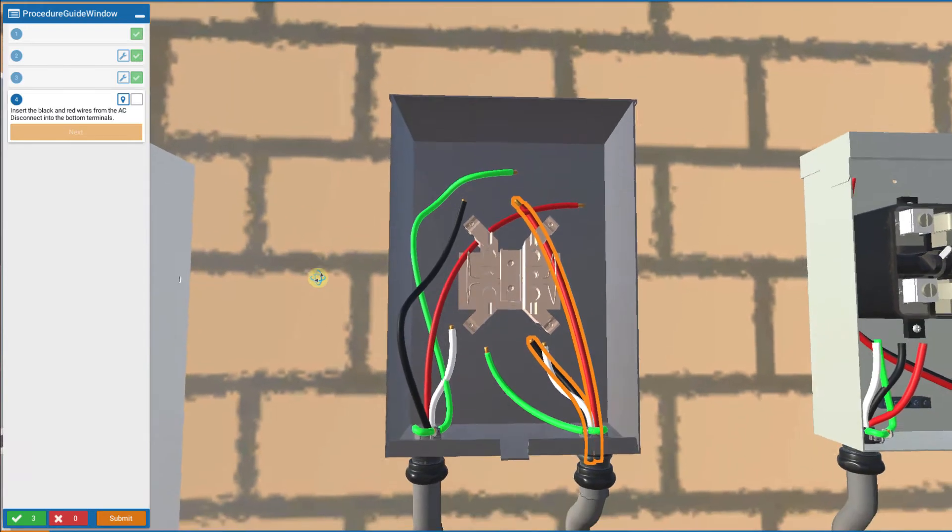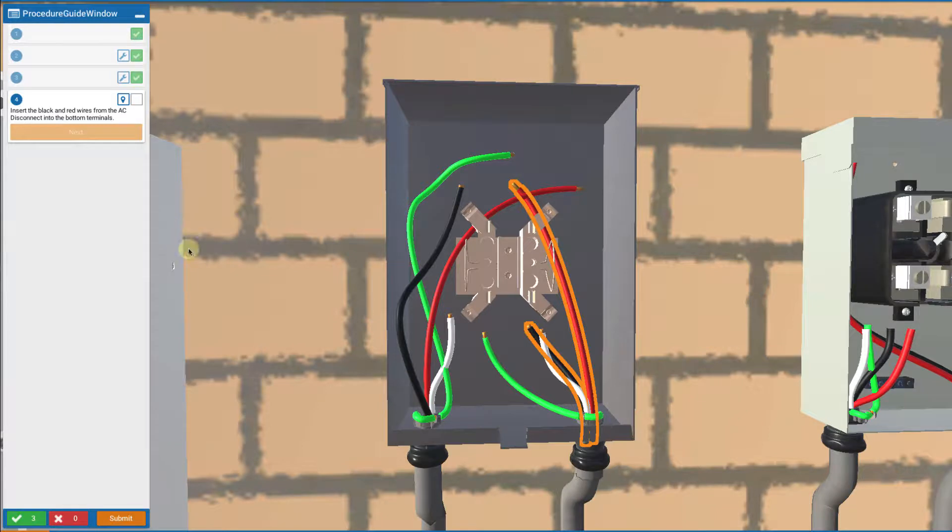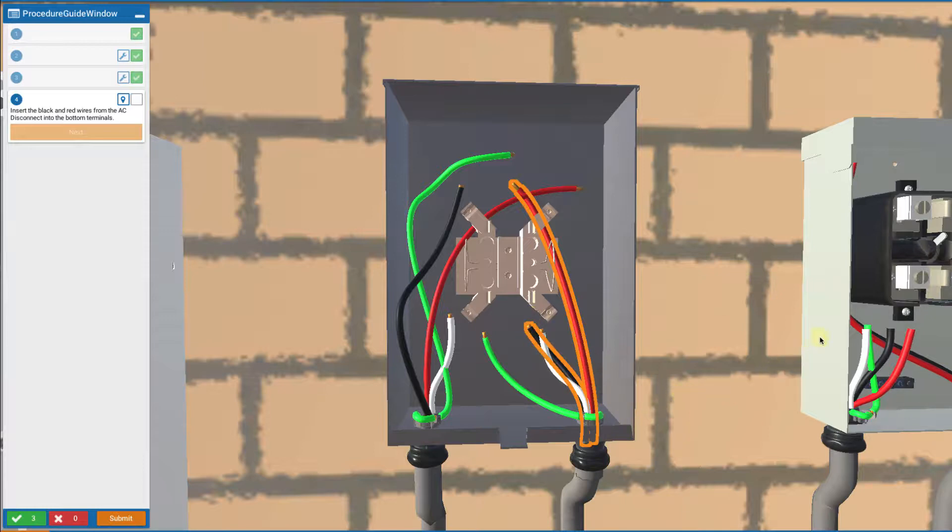Now we get to insert the wires. The key thing is this: the circuit goes from the inverter through the revenue grade meter and then on to the AC disconnect. So we want the wires coming out of the revenue grade meter going to the AC disconnect. Those are these wires.